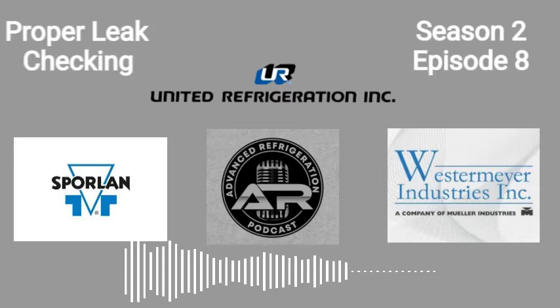I'll go through thoroughly and slowly. I'll go through the glass doors one by one, leaving it in there, walking slow, same with the cases. I'll pop my head up on top. If I've got piping on top of cases, I'll put my leak detector up top. The Stratus has a wand extension on it, which is nice. You could get another 18 inches out of it, I think. I'll sweep on top if there are valve stations up there.